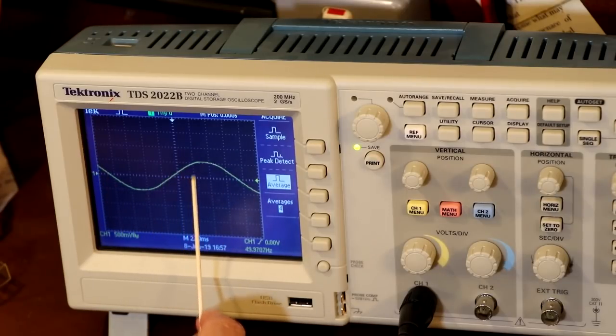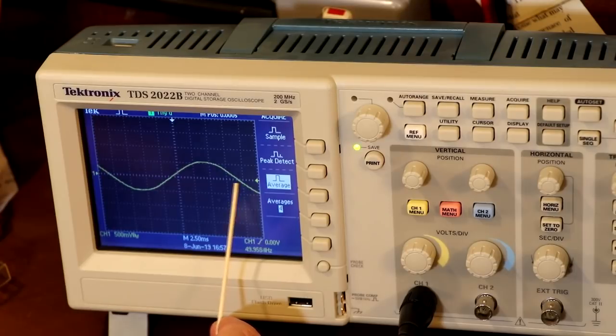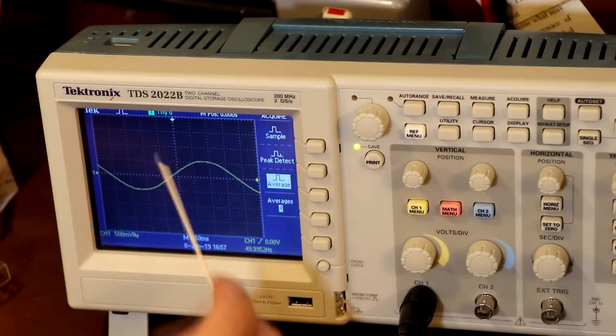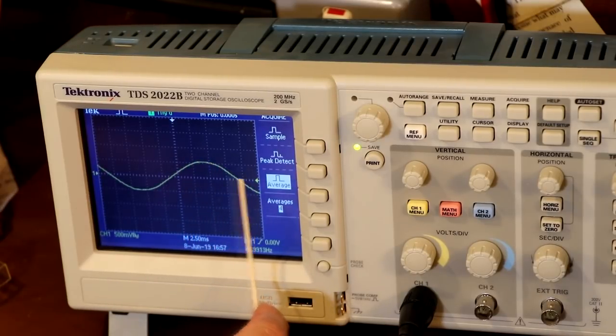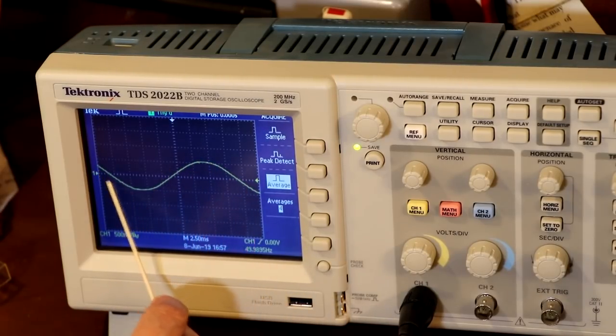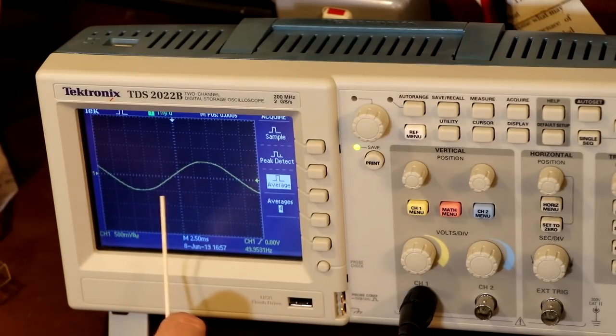The current we're measuring here, we only want it between the zero crossing point and the peak, so that's 500 millivolts. According to the range we're on, 1 millivolt equals 10 milliamps, so that's 500 times 10 milliamps. So the positive current peak is 5 amps, and the negative current peak is 5 amps.